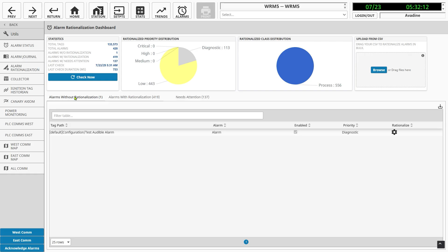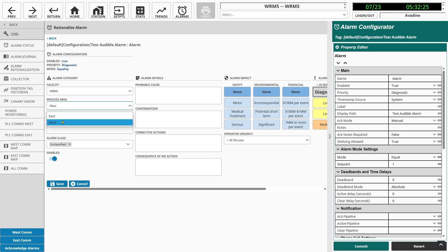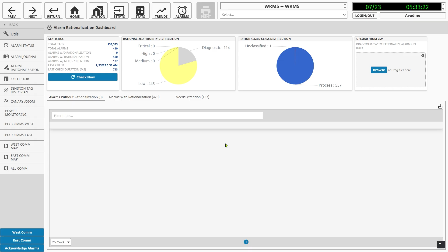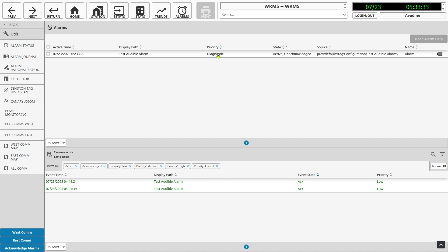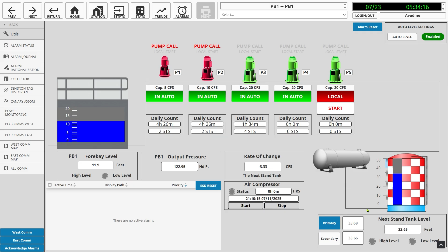We created these primary and secondary loops with all our communication for around the entire west side. And it was very painful because we were having comm issues, since the spanning tree was going back and forth. Every time we started having issues with spanning tree, it exposed that we had a radio problem, and we were able to go find that radio that was causing the issue and fix it.